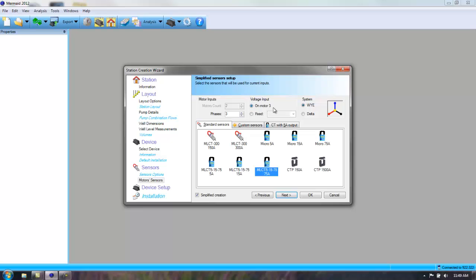Now for motor 3 input, I'm actually going to monitor voltage. And the voltage I'm going to be monitoring is through a step-down transformer, and I'm going to use my Y wiring connections for a Y connection. Because I'm going to assume for this particular station it's a duplex with a 480 volt system, and it most likely is going to be a Y connection, but that's not always true. And there's really no rhyme or reason why we go to Y or delta, but there is a wide range of selections here for the stations themselves.